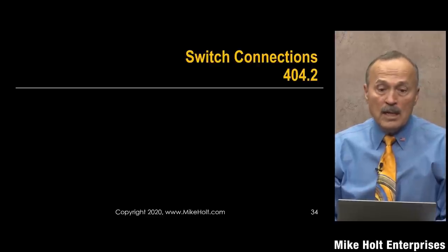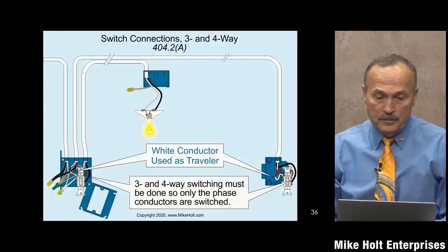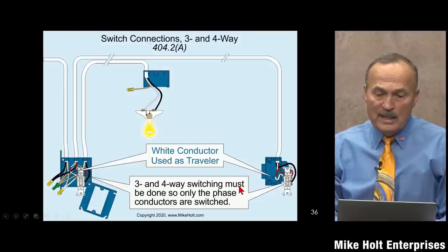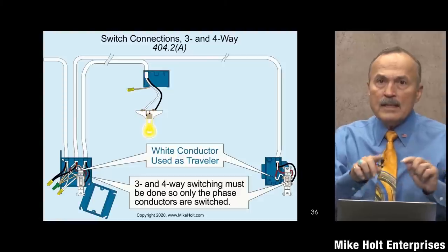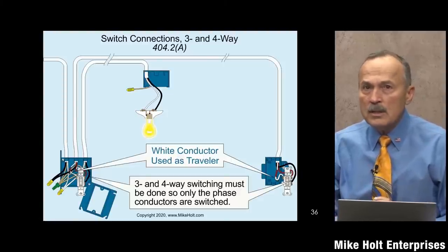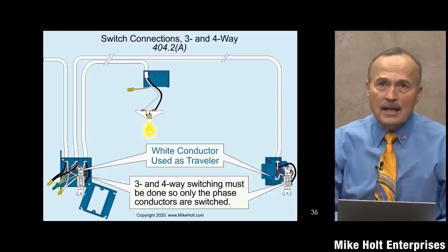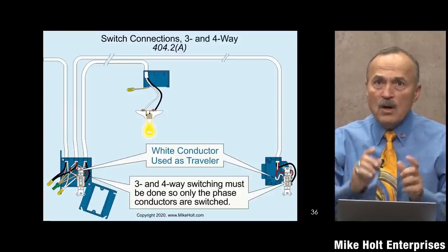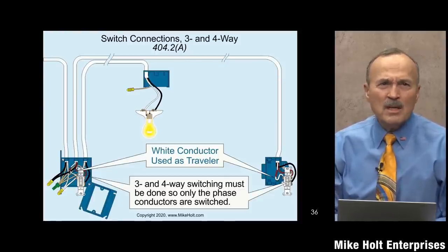Section 404.2, three-way and four-way connections: three-way and four-way connections must be done so that only the phase conductors are switched. I'm not going to get into the wiring diagrams, so you need to get with an electrician to show you how to wire up three- or four-ways. You can find all the different combinations on the internet.